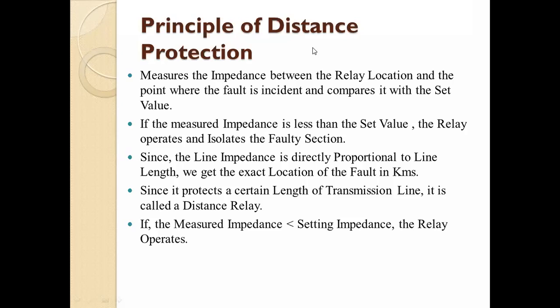The generating station is at one point, and power is supplied at the load end. In between, the line length is more. We cannot protect the whole transmission line if it is 200 or 400 kilometers by connecting only one or two relays at the sending end and receiving end. So we divide that transmission line into sections, or zones.